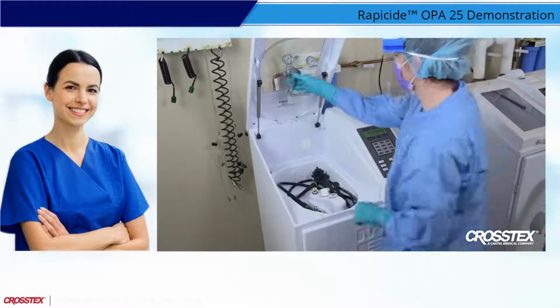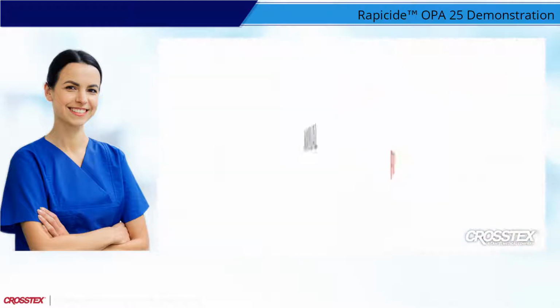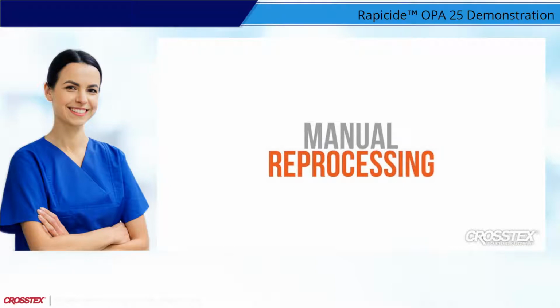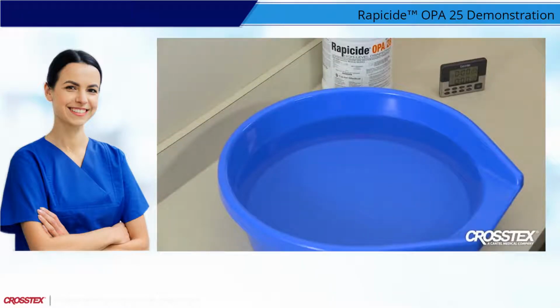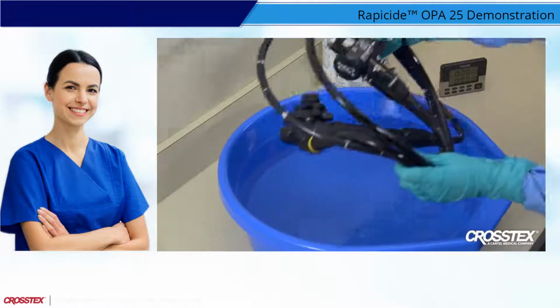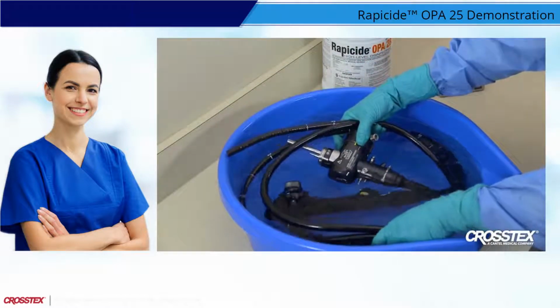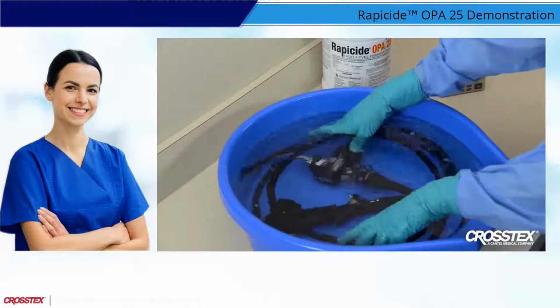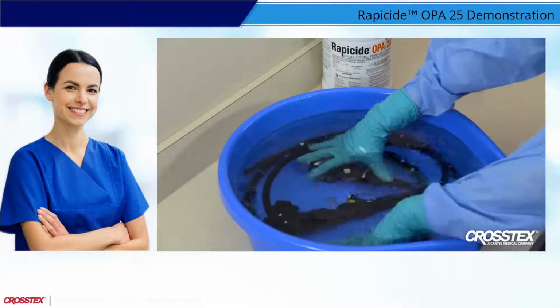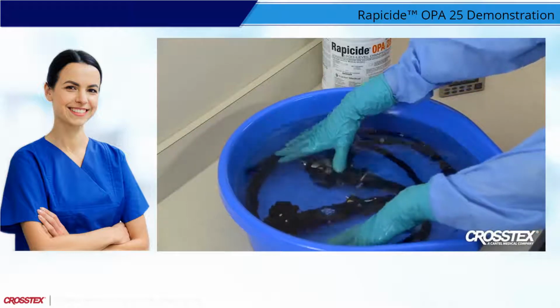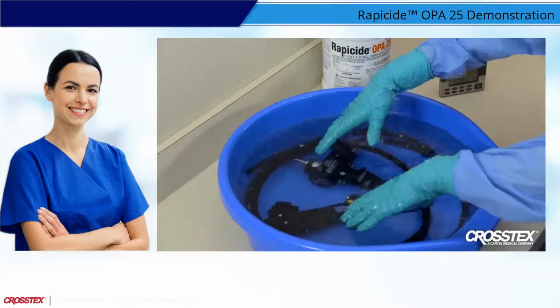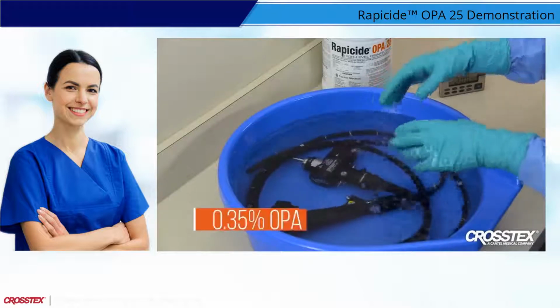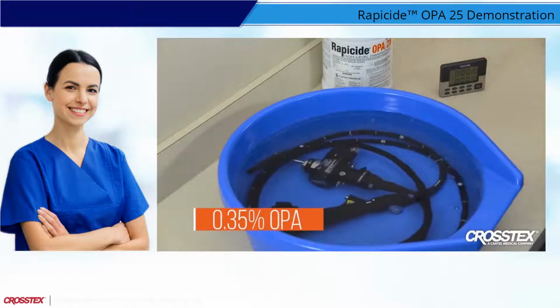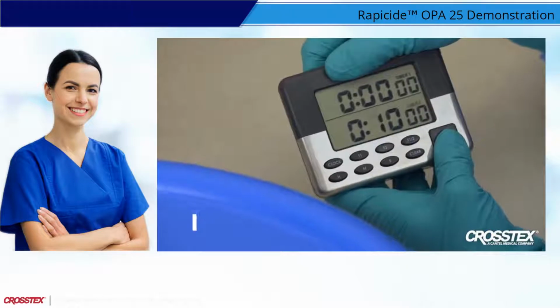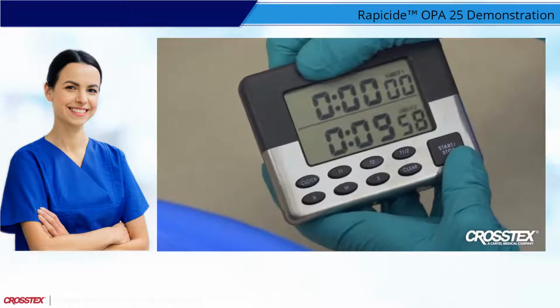Now, let's review how Rapicide OPA28 HLD is used in manual reprocessing. Follow the same steps as before for testing the MRC of the Rapicide OPA28 HLD solution. Place the pre-cleaned scope into the manual holding tank that contains the Rapicide OPA28 HLD solution. Immerse the device completely in the Rapicide OPA28 HLD solution at or above 0.35% OPA for a minimum of 10 minutes at room temperature, which should be a minimum of 20 degrees Celsius.